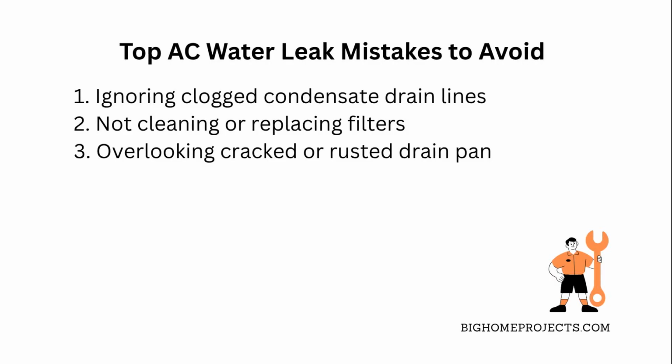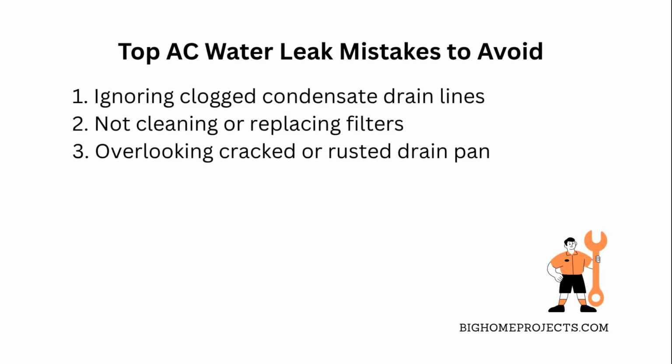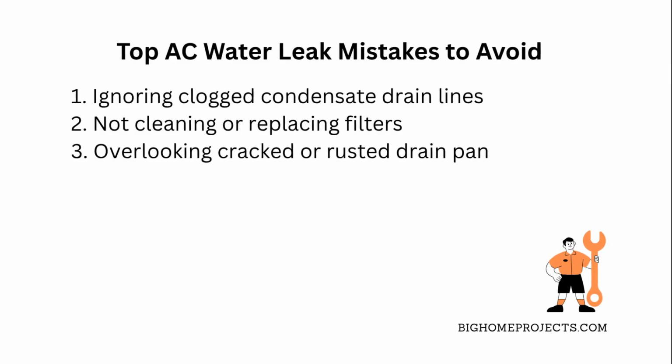Lastly, folks sometimes forget to check if the drain pan is cracked or rusted out, which makes leaks worse. Just replace the pan if you spot cracks or holes to avoid water damage.